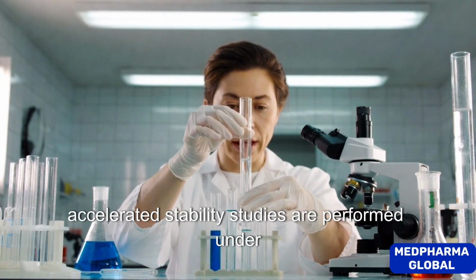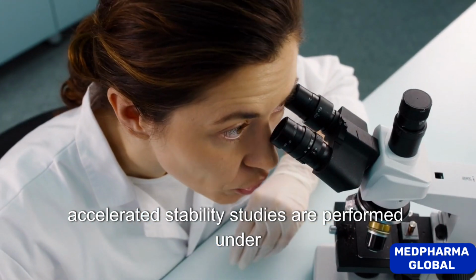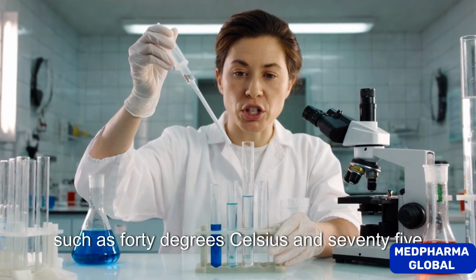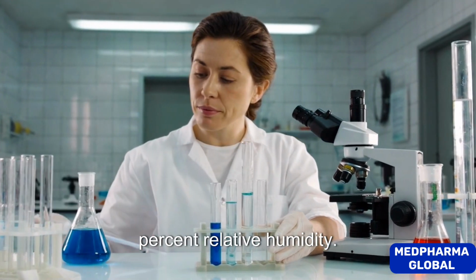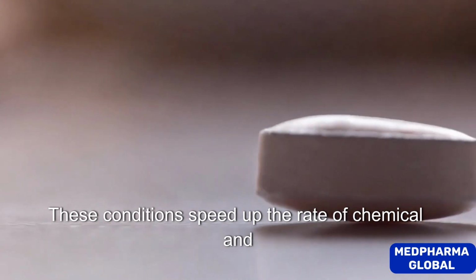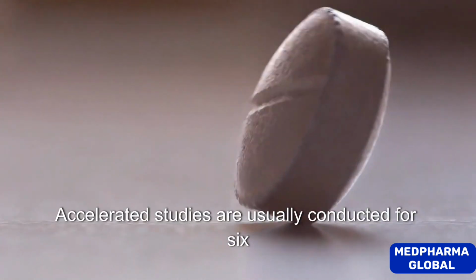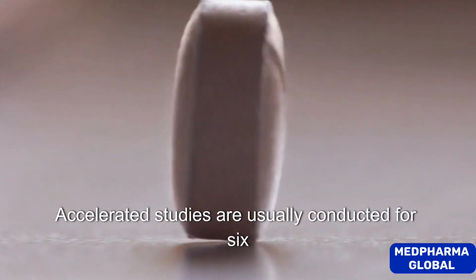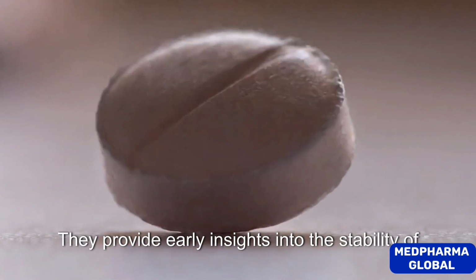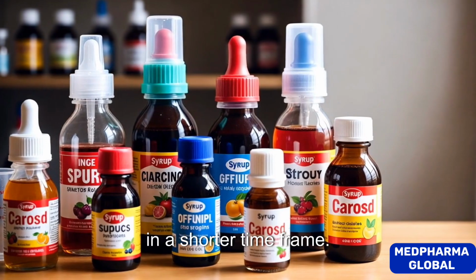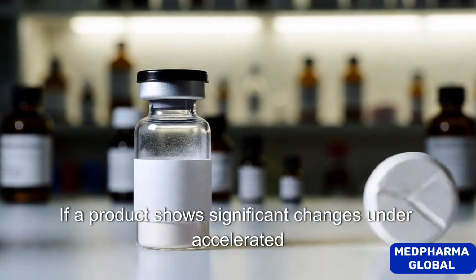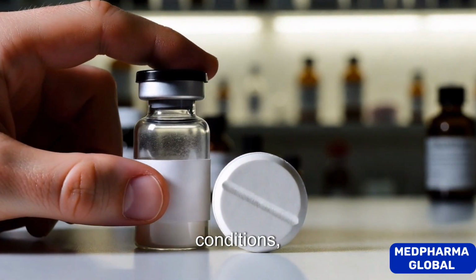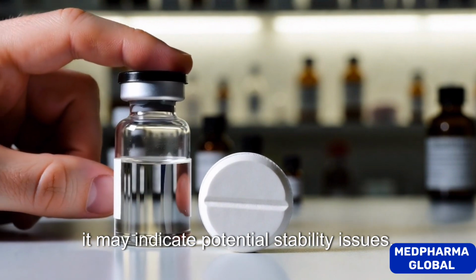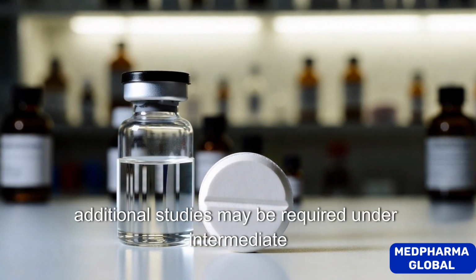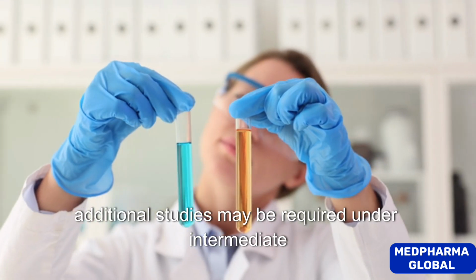In contrast, accelerated stability studies are performed under more extreme conditions such as 40 degrees Celsius and 75% relative humidity. These conditions speed up the rate of chemical and physical degradation. Accelerated studies are usually conducted for 6 months. They provide early insights into the stability of the product and help predict long-term behavior in a shorter time frame. If a product shows significant changes under accelerated conditions, it may indicate potential stability issues. In such cases, additional studies may be required under intermediate conditions.